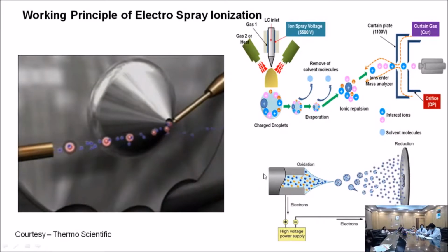Electrospray ionization, or ESI, is a liquid phase ionization technique. The mobile phase is passed through a stainless steel capillary to which a high voltage is applied. The strong electric field generated at the end of the probe, in the presence of a concentric flow of nitrogen, causes the mobile phase to form an aerosol of highly charged droplets.